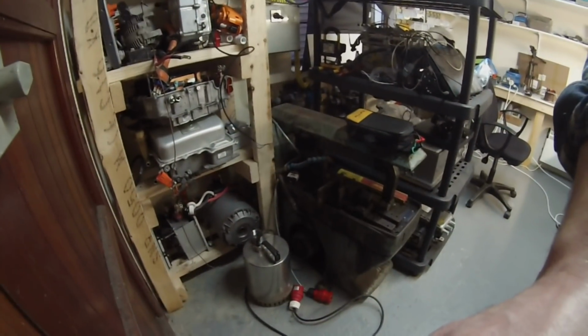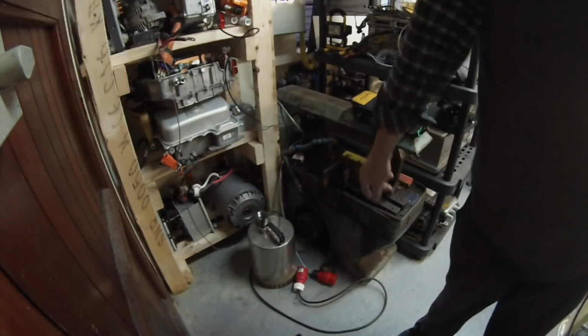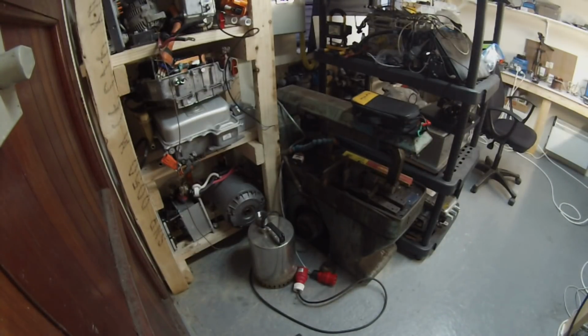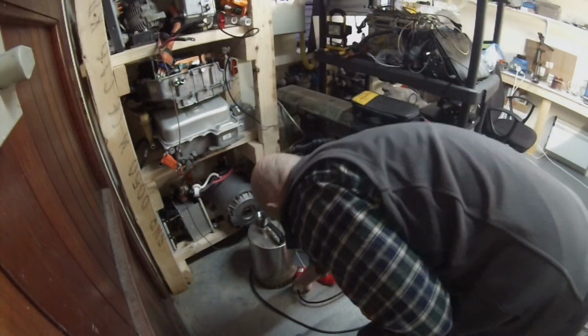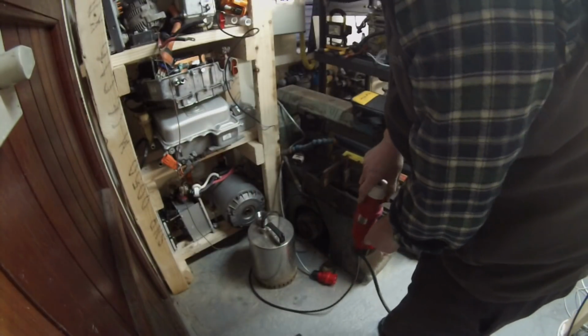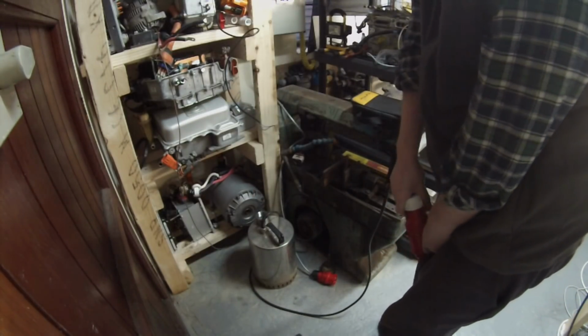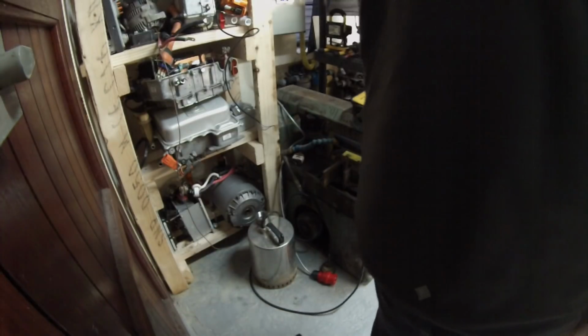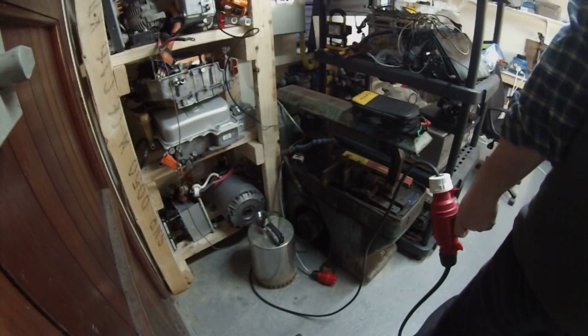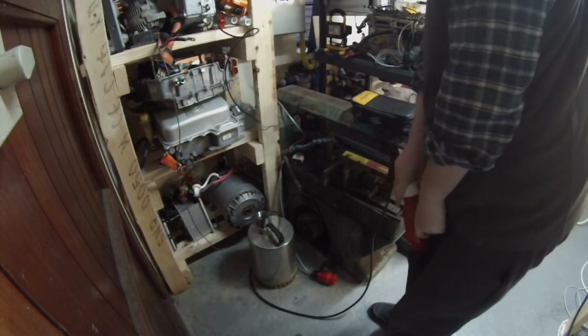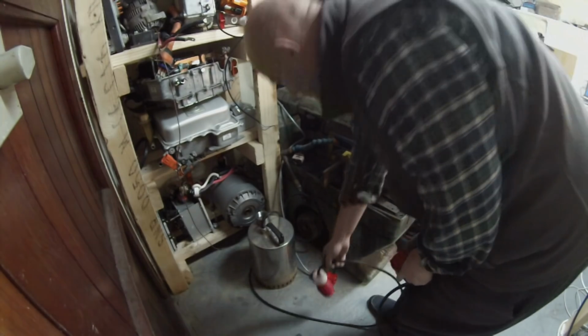So I've got my Grundfos pump here - let's go grab the cable. Unplug the milling machine, here's our Grundfos pump. I'm just going to direct start that. Pump's on, about 1.3 amps at the minute. It's running unloaded, so let that run.